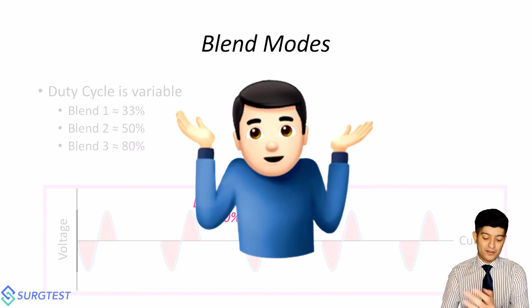But some important questions about the blend mode. Is it necessary and is it a mix of cut and coag? The answer is a very firm no. I'm going to put up all the three curves on your screen right now. So cut, once again, is a low voltage continuous current. Coag is a high voltage low duty cycle current, so it's intermittent with a duty cycle of 6%, and this is where blend is at right now. Once again guys, the power delivery has been the same across all of these currents, right? The area under the curve for cut, blend and coag in total has been the same, but look at the voltage differences. Because coag has to work for a shorter period of time, it has to have a higher voltage delivery to the tissues to compensate for that low duty cycle. And that is responsible for most of the problems that I'm going to be talking about in subsequent slides.